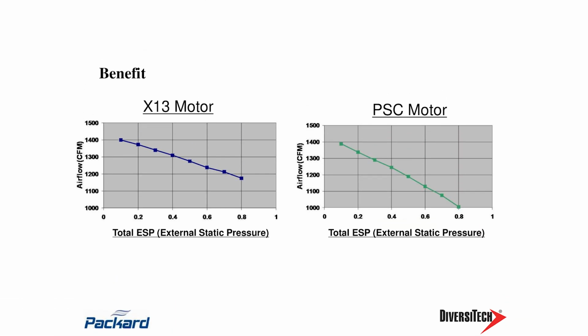Comparing the PSC to a constant torque X13, they look a little more similar to what we see on that curve of the constant airflow, but they do a better job in terms of maintaining air than what a PSC does. How many have heard that if I have a bad static condition, put an EC in there? Who's heard that? Yeah. So you guys who attended Chris's class yesterday, what did Chris say about that? That's hogwash, isn't it? No, that's not going to happen.